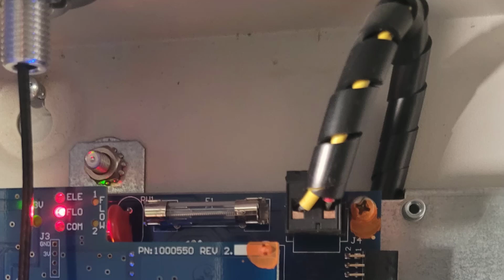TJ, you got anything to add? Make sure you don't put a bigger fuse in there. I've seen customers say, oh, I can't find a smaller 3 amp fuse, so I'm going to put a 5 amp in there. What that does is defeat the whole purpose of the fuse, which is to protect things. If you put a bigger fuse in there, it's no longer going to protect anything.